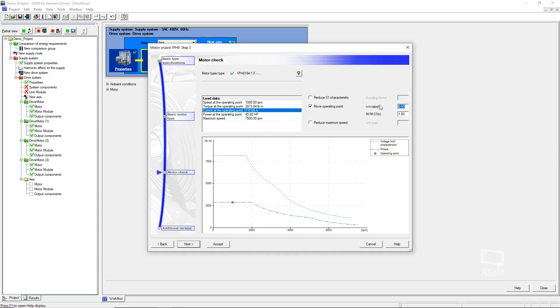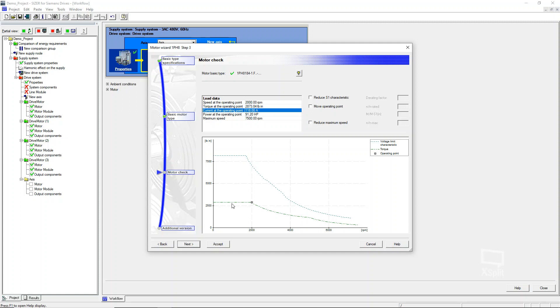Well, for what we're actually wanting to do, we're just wanting to see what the torque of this motor would be at a higher RPM, say 26, 2700 RPM, if you're wanting to speed up your process. So let's uncheck this move operating point. And you'll notice that on this motor, anything below this operating point or this nameplate data, it's just the same. It's a constant torque application.